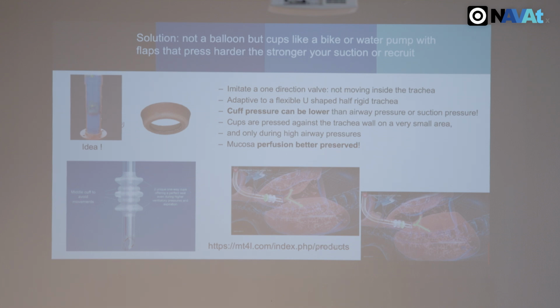But we still have a problem when you aspirate, that fluid might come down in the other direction. So for that, I also designed a cup on the other side. So if you do a suction with a negative pressure of minus 100, this cup will immediately close off against the wall, and there will be no atelectasis.